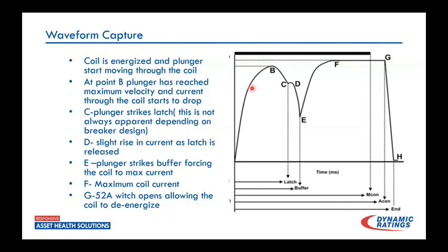This is a really good, or hit the latch, excuse me. And this is a really good reference to understand how that first part of the operation is working. It was something I always looked at. Is this latch point lining up? Especially when you get a slow operator, to understand, okay, am I looking at the plunger movement, the latch, is it not coming off as it should?